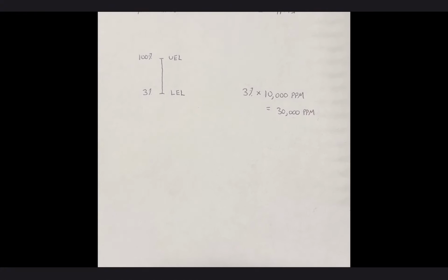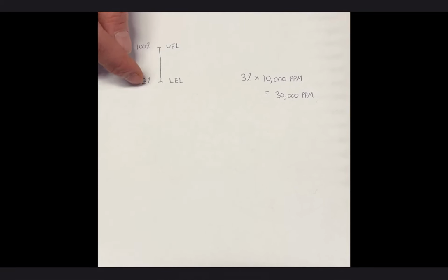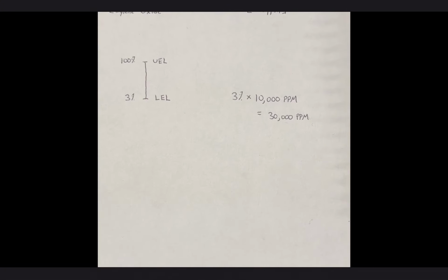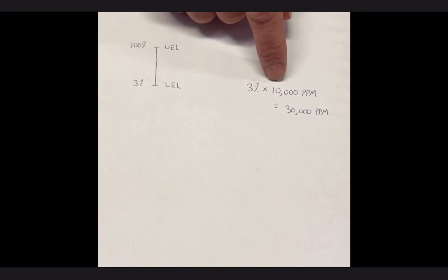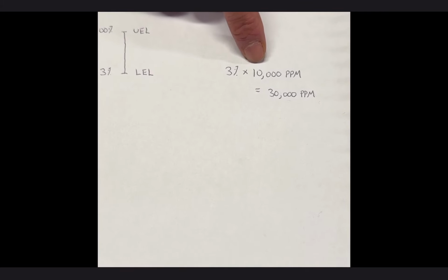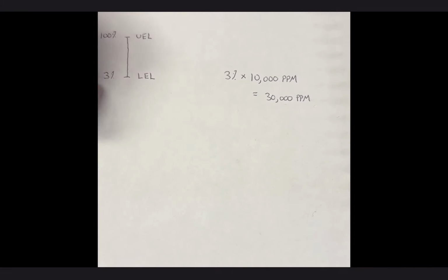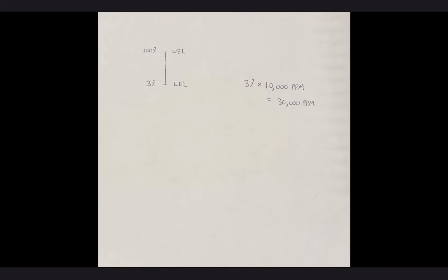So if we're just waiting for our monitors to alarm at the lower limit of 10%, we'll take ethylene oxide, for example. It has an IDLH, immediately dangerous to life and health, meaning you'll have irreversible damage to your body at 800 parts per million, and Ca in front of it means it's a cancer-causing agent. So that's a really low parts per million threshold. The LEL and UEL range from 3% to 100%, showing that it's got a high range of flammability. So if I'm monitoring on here and just waiting for my alarm to go off at the lower limit of 10% of that 3%, if you take 3% and multiply that by 10,000 parts per million for every percent displacing, right? You have 30,000 parts per million. At 10% of that LEL 3%, you'd have 3,000 parts per million. So by the time you get a lower alarm on here, showing you that you're in a flammable atmosphere, you're already dead from the toxins because the IDLH is 800 parts per million.